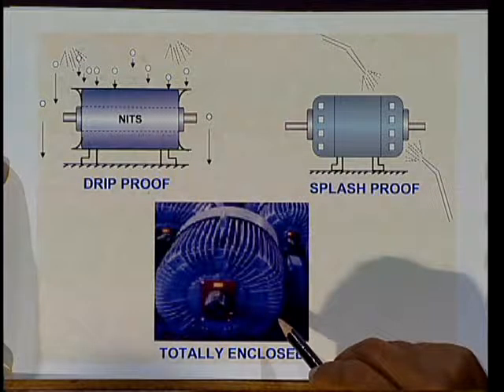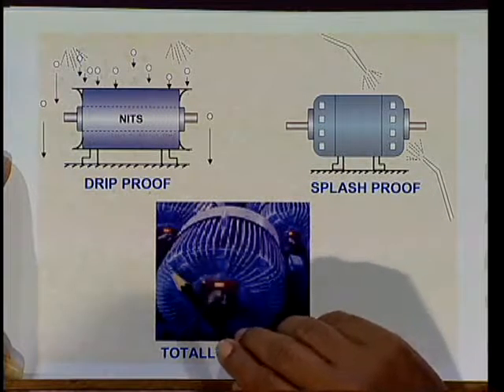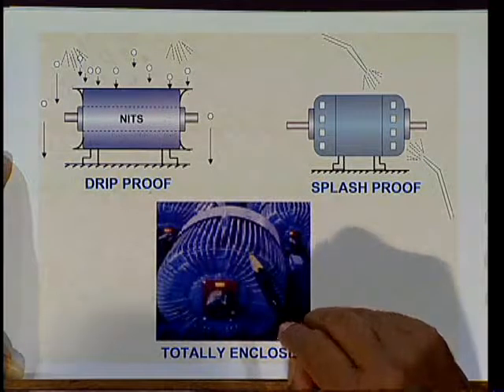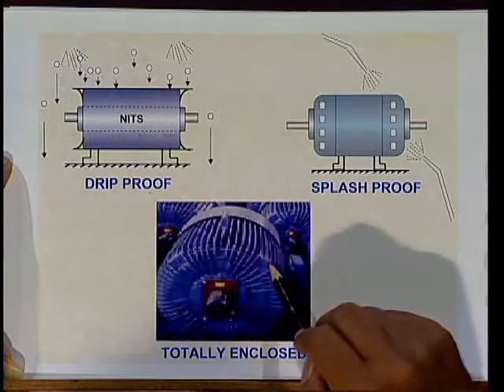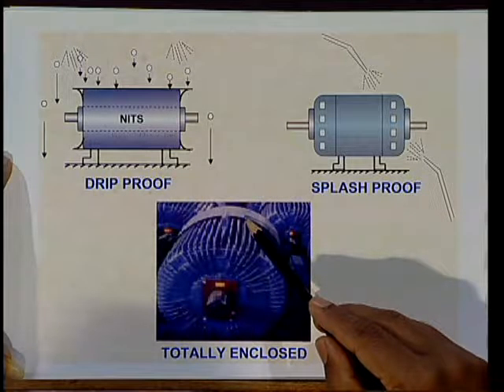In totally enclosed type motors, there are no openings provided. Due to losses, the motor may heat up, and heat is dissipated to the surroundings via hot air or by providing fins on the outer surface of the motor, which increases the contact area. Generally, this type of motor is used where the dust atmosphere is more, such as in pulverization plants, saw machines, and stone crushing quarries.